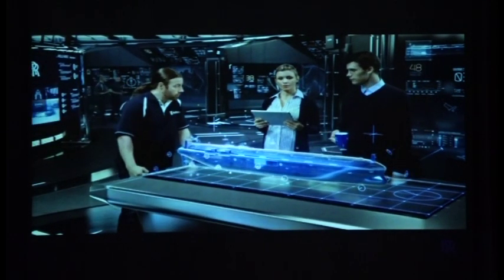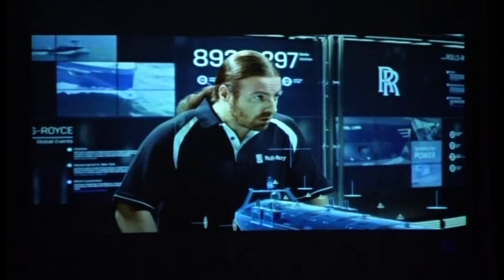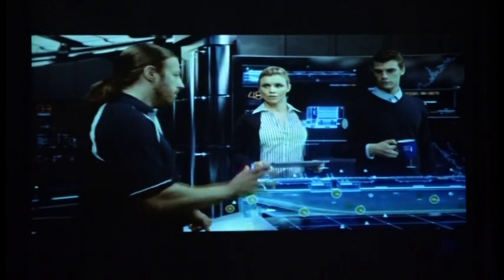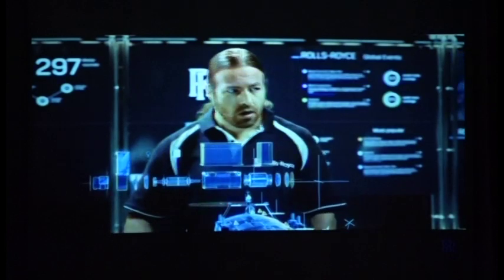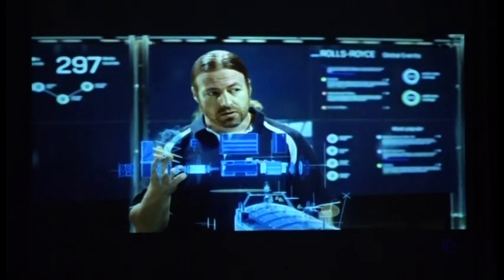We are looking at a vessel with possible propulsion motor failure. We need to decide whether she can sail to port with both motors, or if she needs to shut down the other shaft line. Judging by the motor sound, I'm suspecting a failed feedback sensor. We can bypass it by changing to model-based open-loop feedback. And I'm positive she can then sail to port with both shaft lines operational. But I want to hear your opinions.